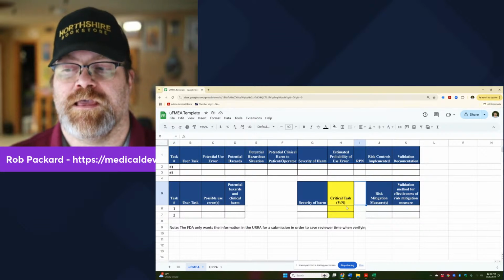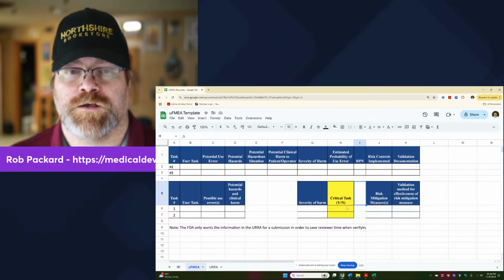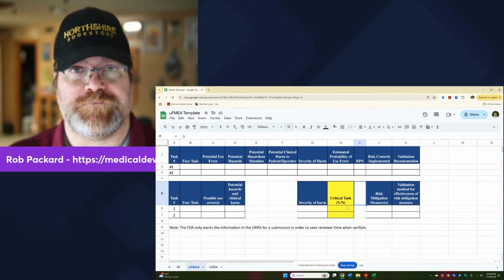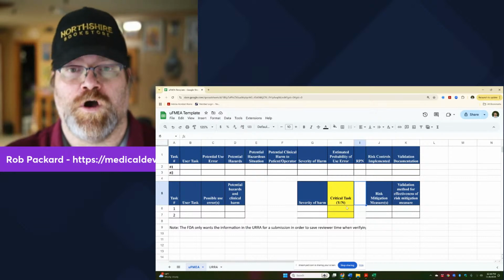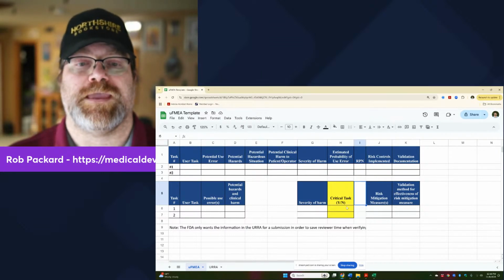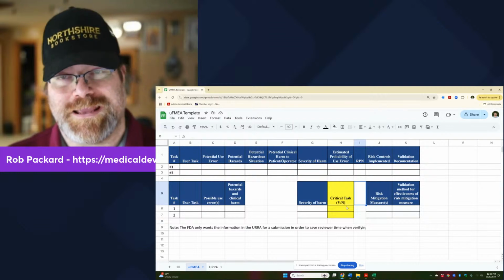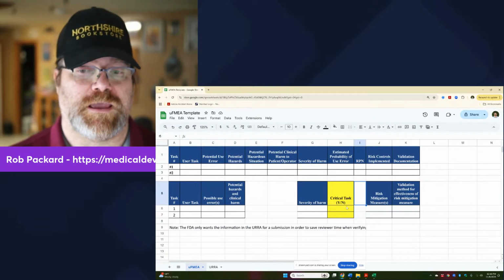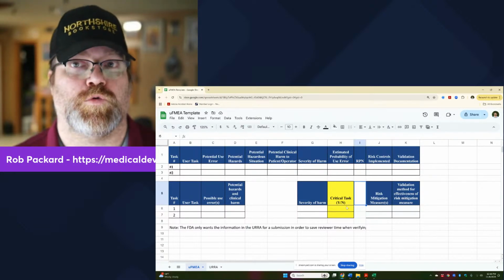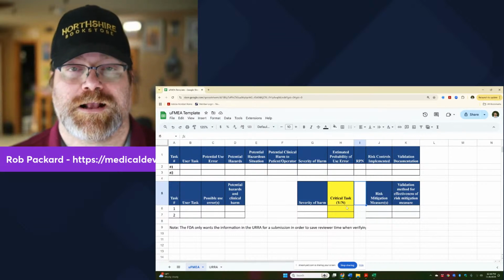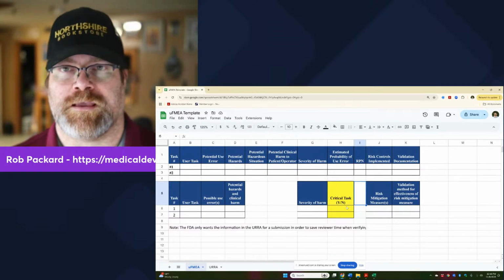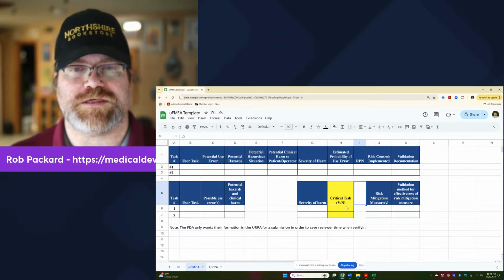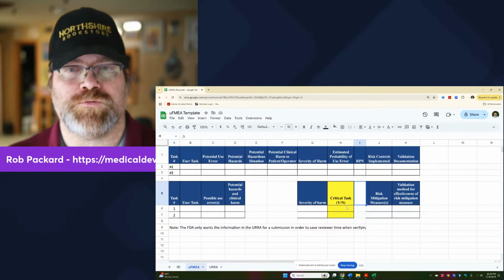If you've read what the FDA guidance says, they only want you to consider the severity. So if you have a typical 5-point scale for severity, typically 3s, 4s, and 5s are reportable. Death being a 5, 4 being a permanent serious injury, 3 being a non-permanent serious injury or injury, and 2s being a non-serious injury and definitely not permanent, something that's more of a superficial scrape or cut, something like that, and 1s being no injury at all, cosmetic delay, something like that. Everybody uses slightly different wording and scales, but in general, that's what the FDA is used to.